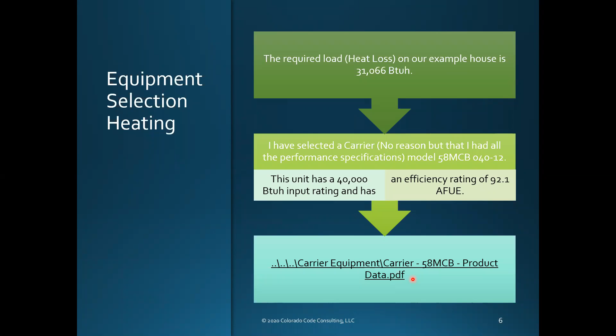So here we're talking about the derate. We started with that. We got 40,000 times our 0.921, and then we did another 10%, and that's where we got that. The key is that Manual S does have generic derate factors, but don't use that. You're going to get the footnotes in the performance data. They will actually tell you exactly what it is for derate per altitude. So don't use anything generic. Use exactly what they say.